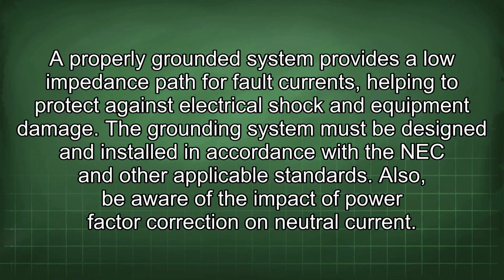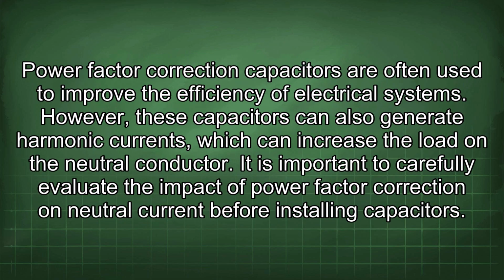Also, be aware of the impact of power factor correction on neutral current. Power factor correction capacitors are often used to improve the efficiency of electrical systems. However, these capacitors can also generate harmonic currents which can increase the load on the neutral conductor. It is important to carefully evaluate the impact of power factor correction on neutral current before installing capacitors.